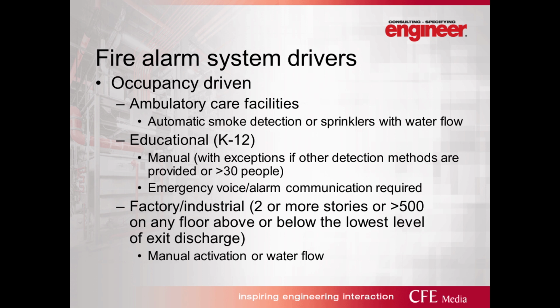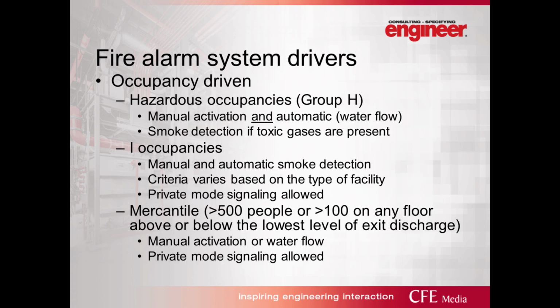So factory and industrial occupancies that are 2 or more stories or greater than 500 people on any floor above or below the level of exit discharge would require a fire alarm system. So, you could have a single-story industrial facility that doesn't require a fire alarm system. It may actually be sprinkled, but you would not necessarily require occupant notification. Now, it's oftentimes provided, but from a code basis, it would not be required.